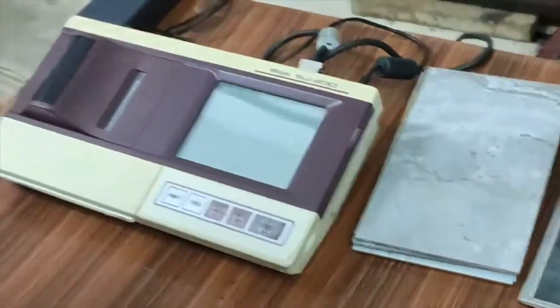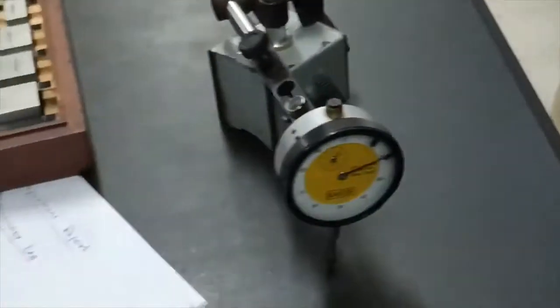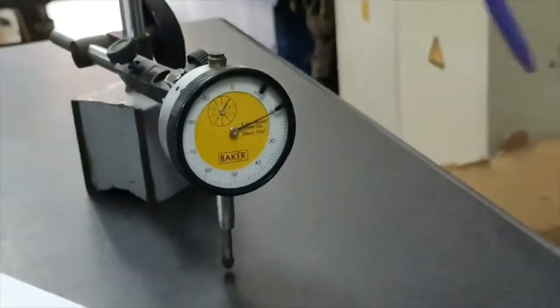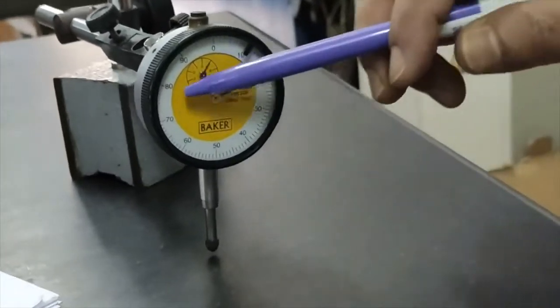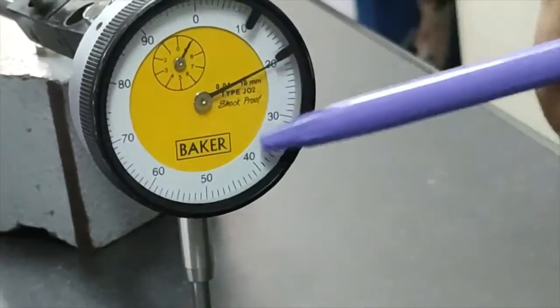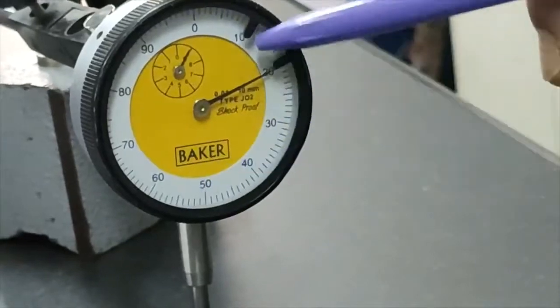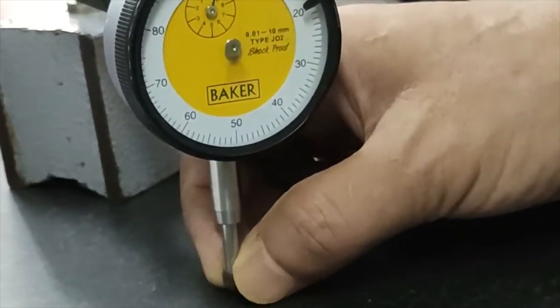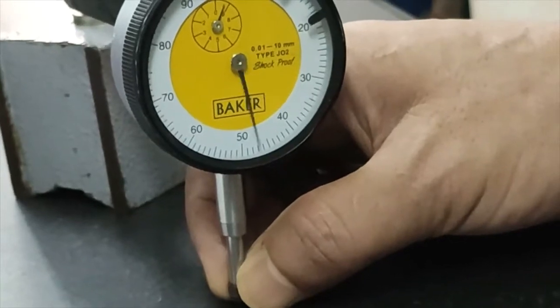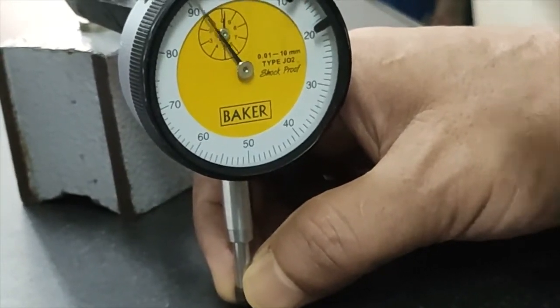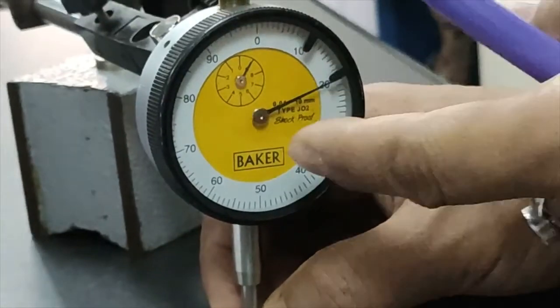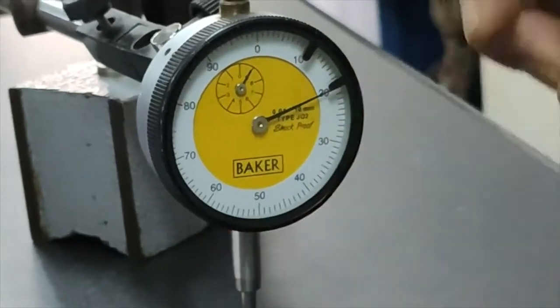Now first come to dial indicator calibration. We have one dial indicator with 100 divisions gradation and this is the plunger. You can lift it out. If you lift 1 mm it will complete one round rotation. So 1 mm by 100 divisions gives 0.01 mm as the least count.